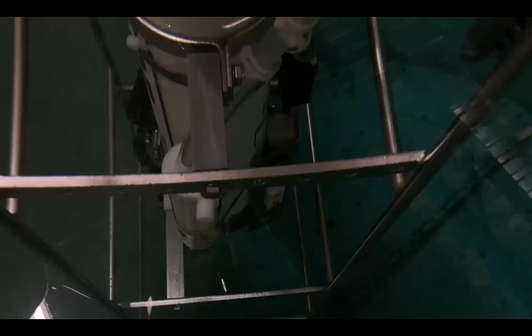So when all the bubbles are released from the instrument, the water then flows through the SBE 5 pump, and then the water gets out of the 19 plus V2 from the pump exhaust.